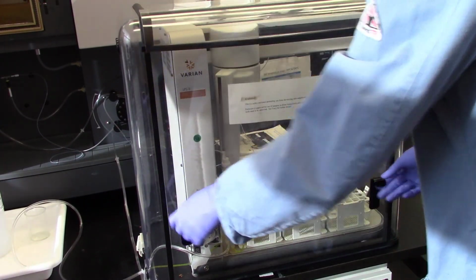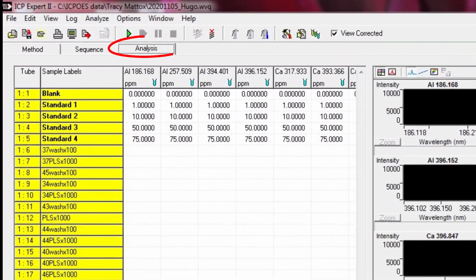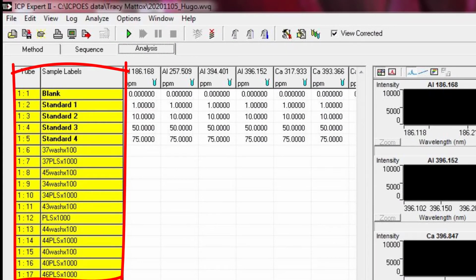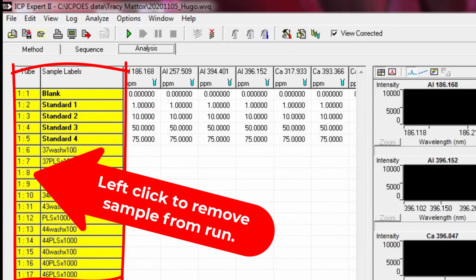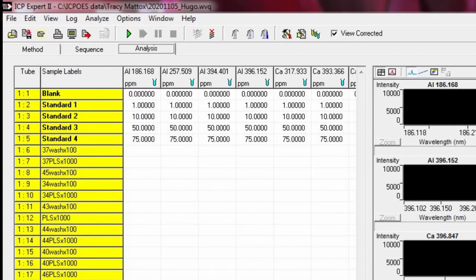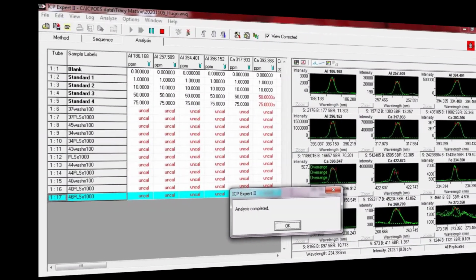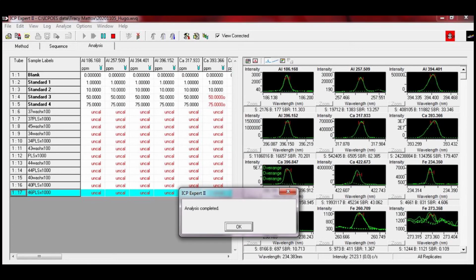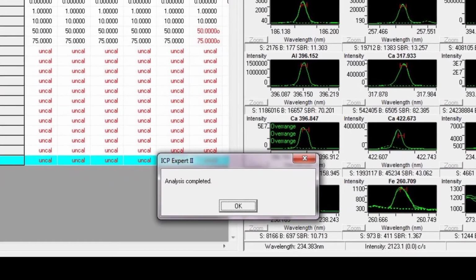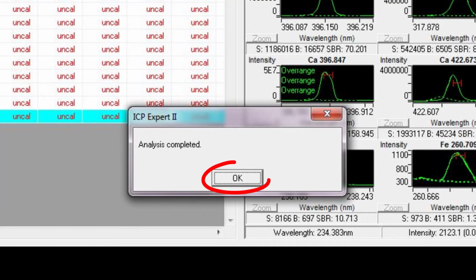This step is required anytime the system is running so that your hands will not be hurt accidentally by the moving needle. In the Analysis tab, be sure that all of the standards and samples you wish to run are highlighted in yellow. A left click on the tube number will gray out a line so that the tube will not be run, and another click will bring it back to yellow. Once you are happy with the sample lineup, click on the green play button on the top of the screen to automatically run your samples. It takes about 90 seconds to collect data for each tube. When the run has completed, you will need to press OK in the Analysis Completed pop-up window.